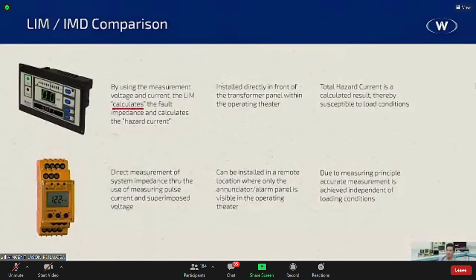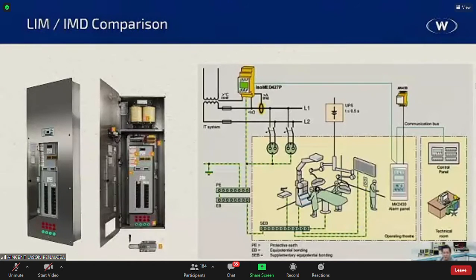Now, of course, due to the measuring principle, accurate measurement is achieved independent of loading conditions. What we're looking into really is insulation, even insulation of the equipment itself. If you plug something in there that has bad insulation, we will find out. It will give out an alarm. And a more visual comparison, on the left side of your screen, that's basically how a line isolation monitor panel looks. You have the circuit breakers, you have communication there if you want. And then you also have the transformer. As you can see, it's a very small transformer, again no more than 10 kVA.